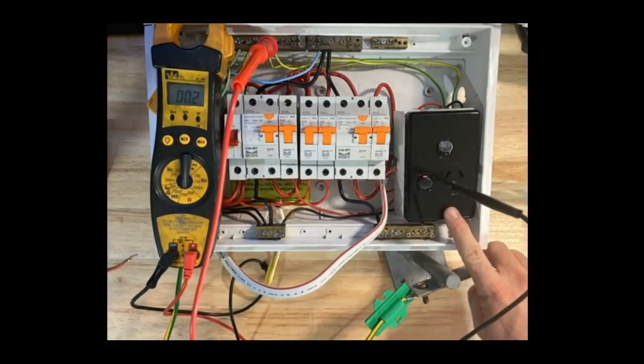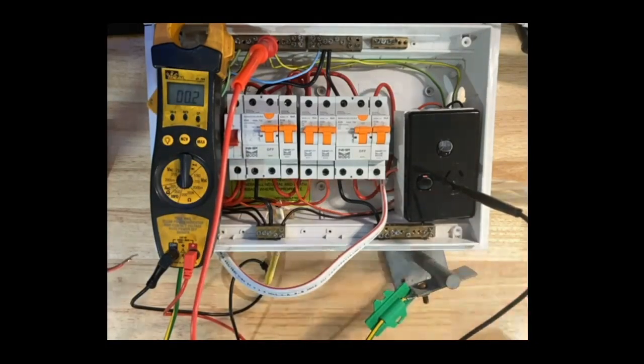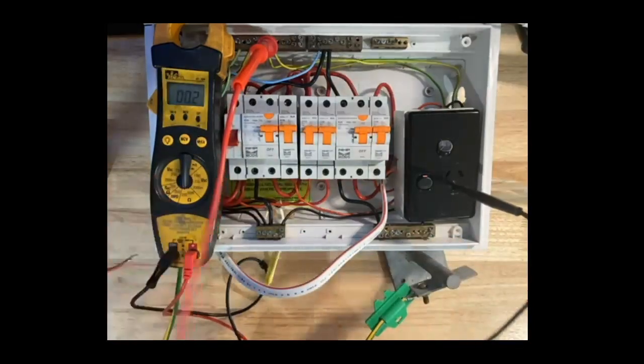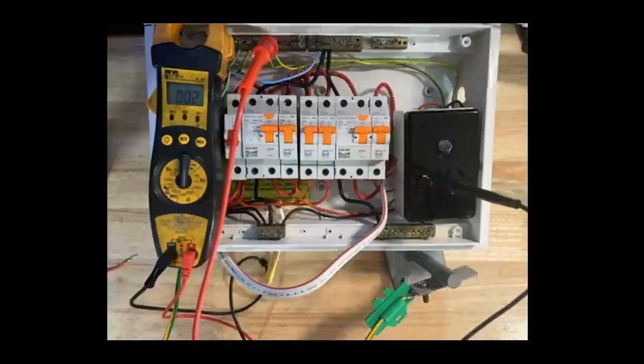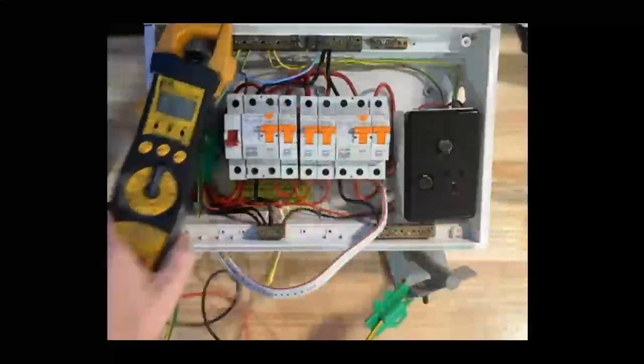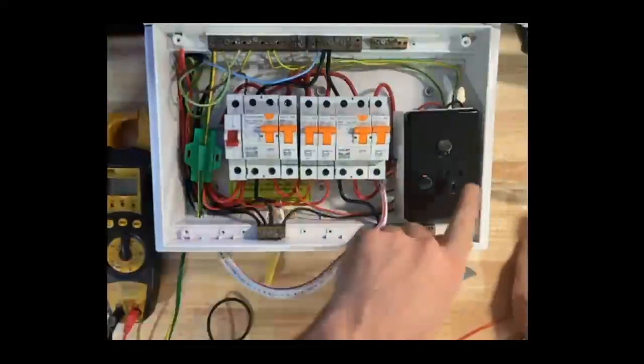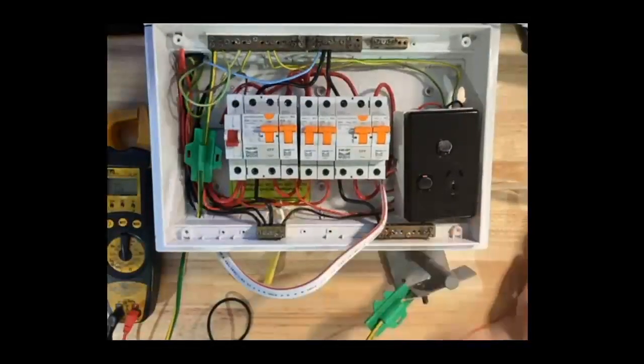end of the house, or even on the other side of the same room as the switchboard, my meter leads are not long enough to do that, and you would be right. This is quite a difficult test to do with standard meter leads if I need to go all the way around the house and test the earth connection on every socket and again on every lighting point, etc., etc. In fact, it would be almost impossible.